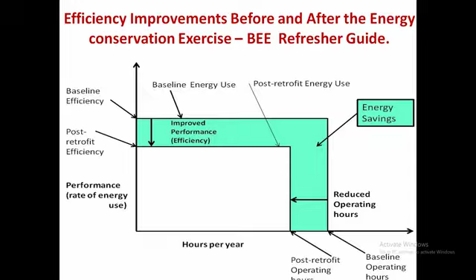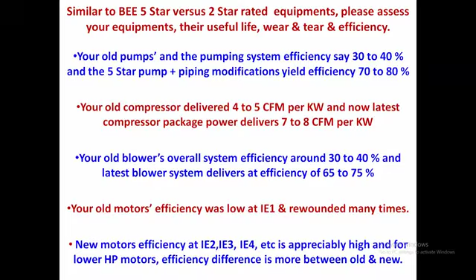So pumps are around 30 to 40%, the 5-star rated pump around 70 to 80%; the compressor around 4 to 5 CFM, whereas the new one is 7 to 8, almost doubled. The blowers are around 30 to 40%, against around 80. These are the areas: the gap between the efficiency of the existing machine or utility and the efficiency of the new energy efficient utility is around 40%. We can very much address the gap. I don't say they have to replace totally. First, let us make them understand to run the machine with energy efficient loading and try to achieve minimum loss. If that is not possible, go for replacement.